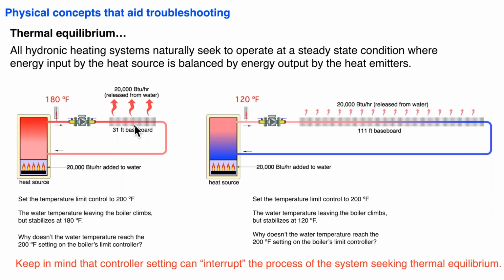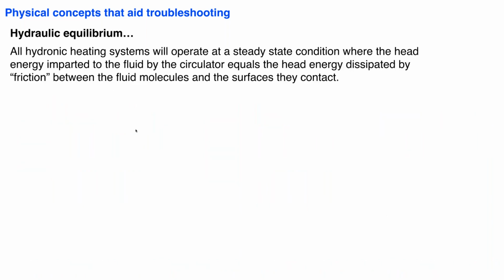And there are many systems out there that without a high limit control would likely go to temperatures higher than what is deemed safe. I tend to like temperatures no higher than 200 degrees. If we had a loss of pressurization, we're below the atmospheric boiling point of water, so we aren't going to get a steam flash. But again, take the controls out of the picture, think about thermal equilibrium. Now, the other equilibrium that hydronic systems seek is called hydraulic equilibrium. And it's the same concept.